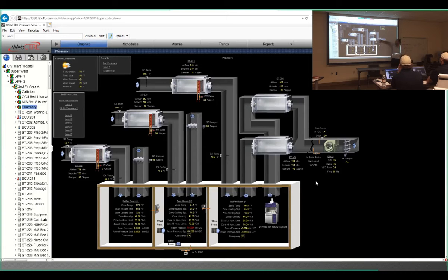As our exhaust fans maintain 1.5 inches of duct static, these 2 VAVs are controlling this room pressure here and here. Now this one's controlled into the return, but these 2 have to be exhausted, so they're controlling going back to the exhaust fan.